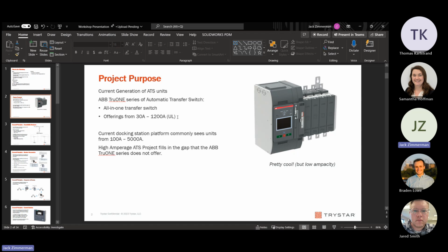So we can see this high amperage ATS project as something that fills in the gap that the ABB TruONE series does not offer, because, as I show in my caption here, the ABB TruONEs are a really cool piece of technology, and they include a lot of things that inspire the design for this unit, but they're just very low ampacity - they can't handle most of the stuff we put in a pad mount. It's a way to fill the gap, and especially when we get into talking about one lines, the TruONEs are not service entrance rated and they're not an overcurrent protection device, which our ATS design brings all of that in. We have ground fault, GFI, and all of those things. So even though it's a really interesting and cool unit, it doesn't fulfill all of our needs and doesn't fulfill the ampacity requirement there.